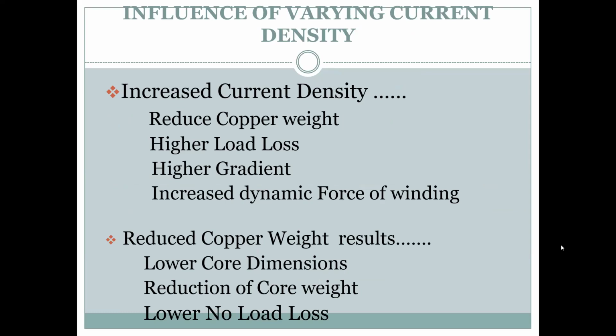If I increase the current density, then I am using the circumference of the copper conductor to the maximum. The current will flow almost through the surface area. But if they restrict me with a lower current density, then the copper conductor will be only 30% or 40% used. The balance is wastage. Wastage means, I may call it an ignorance factor, or it is for preventive maintenance. Earlier, the customer used to give me a limit on the weight of the transformer, the Russian technology, they go by the weight. So reduce the copper weight, then I can give him, but if I use a higher current density, then there is higher load loss and higher temperature gradient.